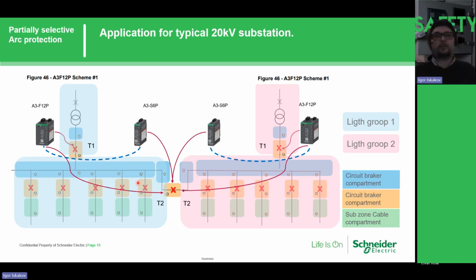So for this application, we can use the same A3 unit. It needs fewer units in this case, because we also have a unit with more sensors and fewer trip contacts, but it fits the needs of some old switchgear where you can also implement easy arc flash protection. So here I use only 2 units for the left part of the switchgear and 2 units for the right part. And if you remember, in the full selective, it was more, if I'm correct, 3 or 4 units for full selective protection.